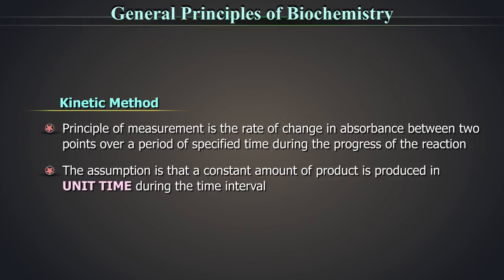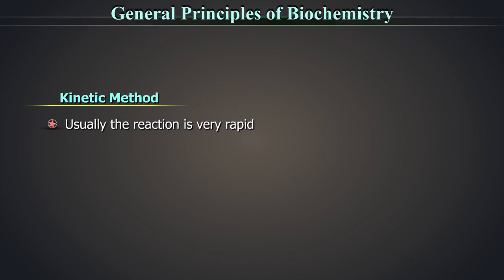The assumption is that a constant amount of product is produced in unit time during the time interval. This is also rate chemistry but the principle depends on the progressive reaction. Usually, the reaction is very rapid and thus, reaction time is short to avoid any danger of enzyme degradation. These tests are performed with a pre-incubation phase, usually done inside the equipment as programmed into it, during which any substances in the sample which might interfere with the test would have fully reacted with the reagent system.